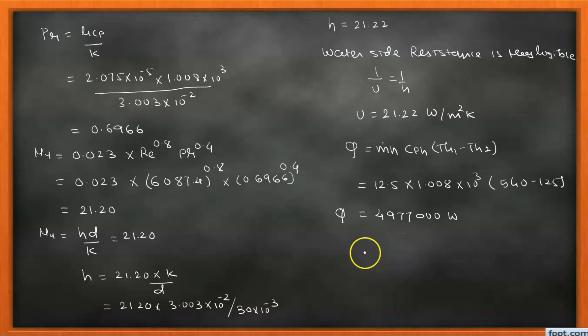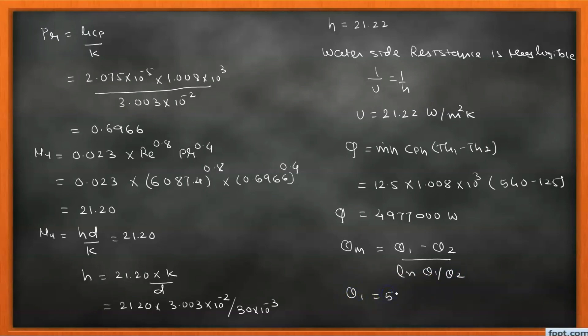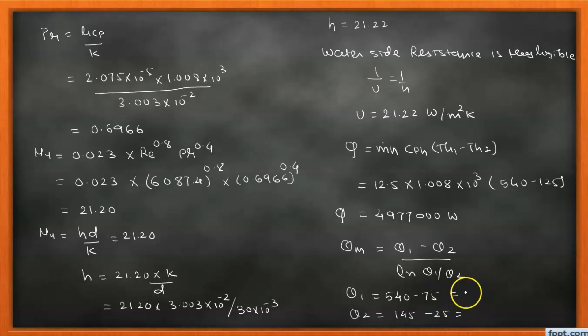We now calculate the LMTD: θ_m = (θ1 − θ2) / ln(θ1/θ2). For a counterflow arrangement, θ1 = 540 − 75 = 465°C and θ2 = 145 − 25 = 120°C. Substituting these values gives θ_m = 254.69°C.